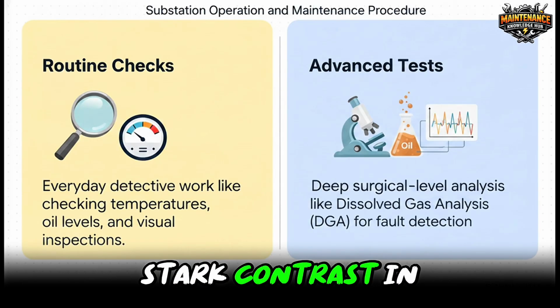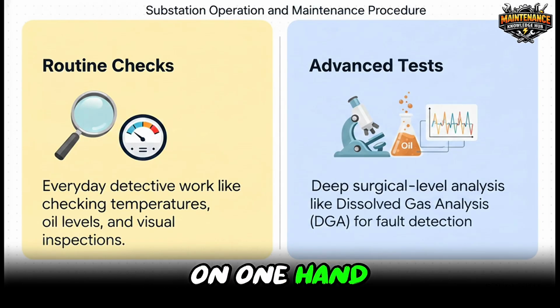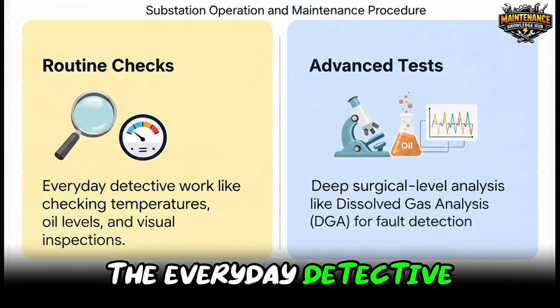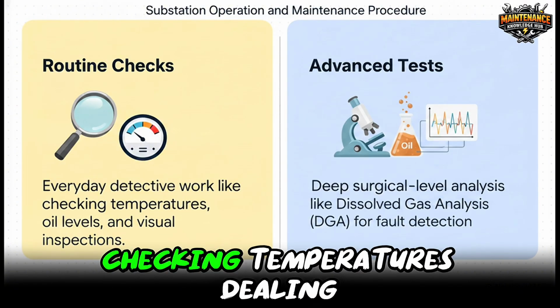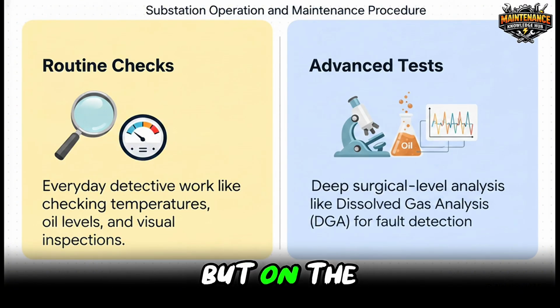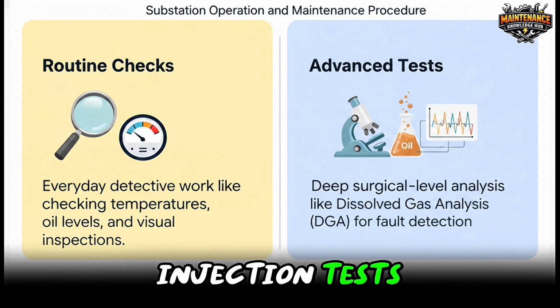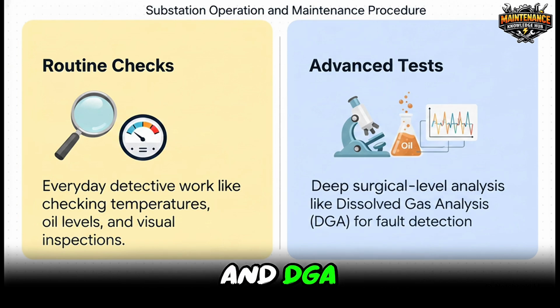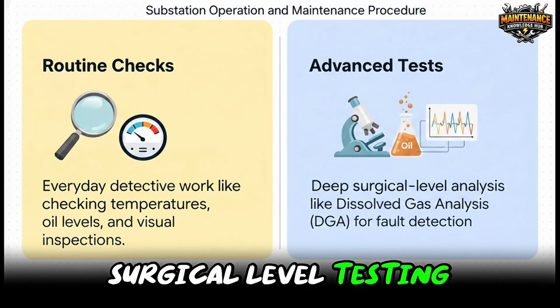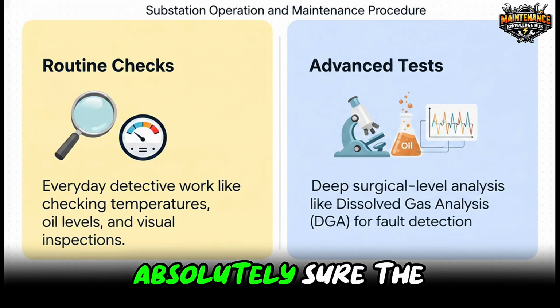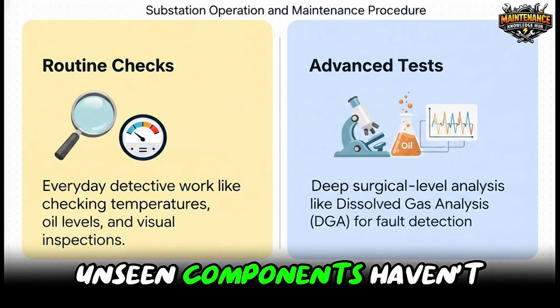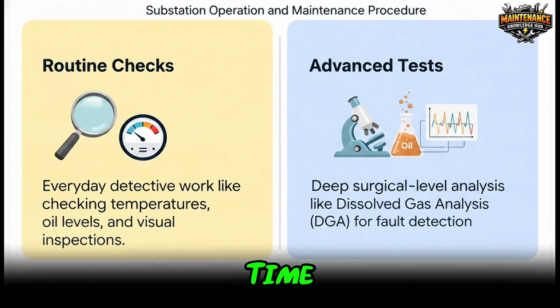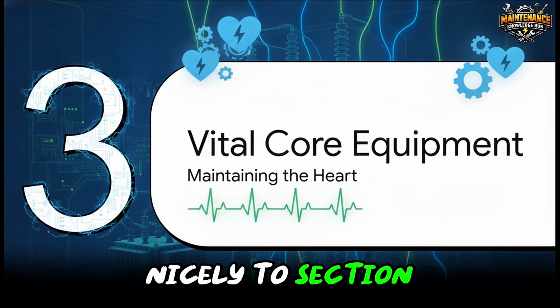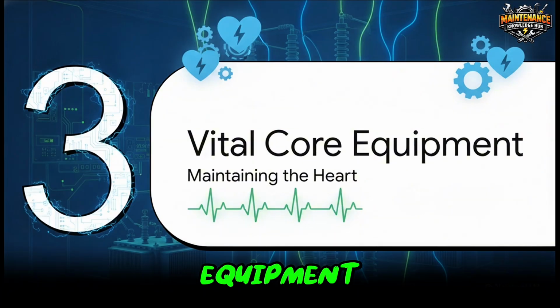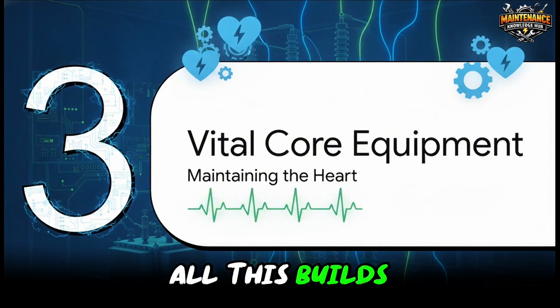There's a really stark contrast in these procedures. On one hand, you've got your routine checks, the everyday detective work of monitoring oil leaks, checking temperatures, dealing with alarms. But on the other side, you have the advanced diagnostics, things like primary injection tests, tan delta tests, and DGA. This is deep, surgical-level testing executed annually just to make absolutely sure the internal, unseen components haven't invisibly degraded over time. Which brings us nicely to Section 3, Maintaining Vital Core Equipment. Let's see how all this builds.